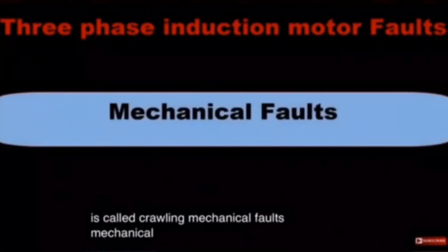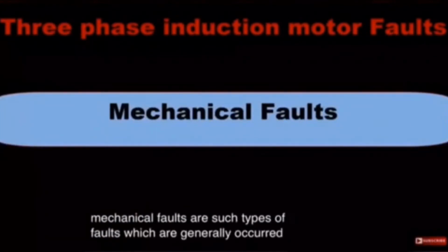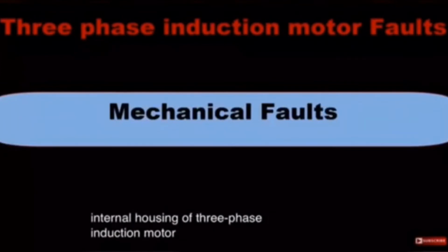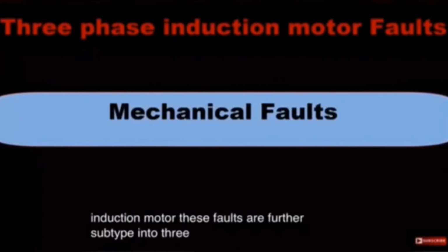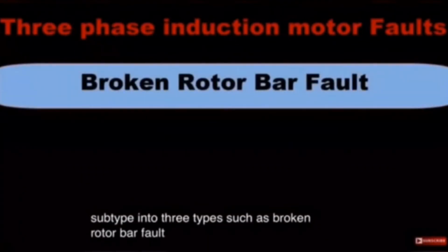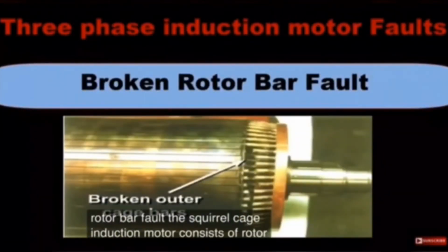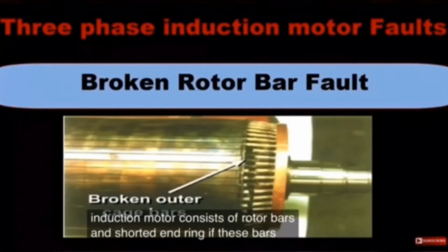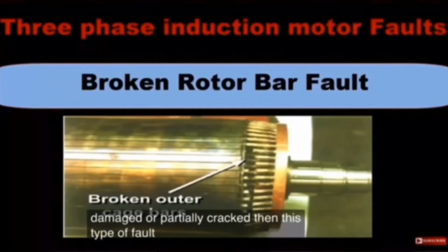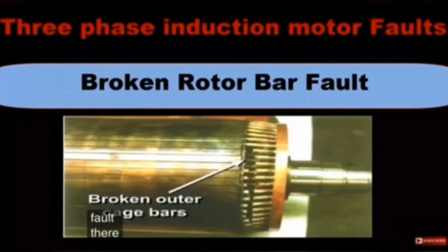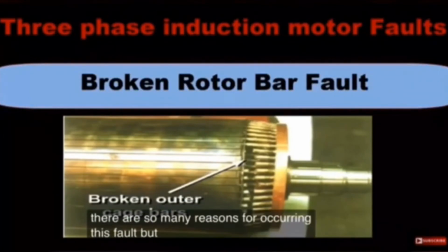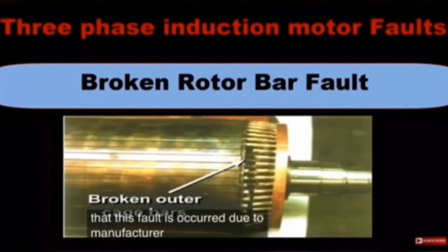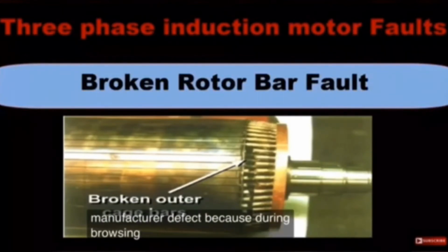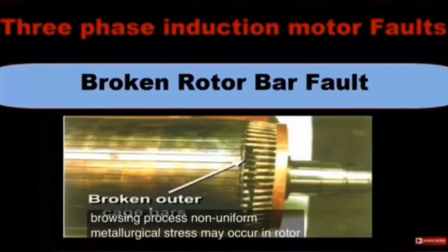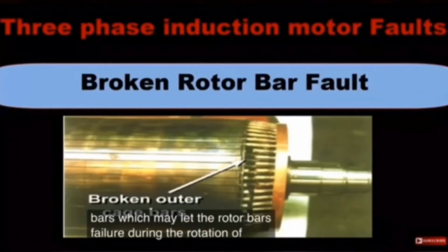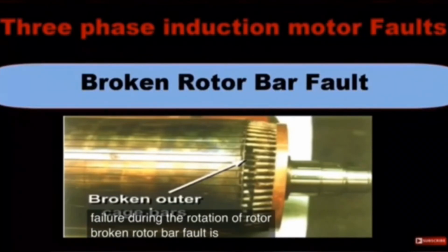Mechanical faults. Mechanical faults are such types of faults which generally occur in the internal housing of a 3-phase induction motor. These faults are further subdivided into 3 types such as broken rotor bar fault. The squirrel cage induction motor consists of rotor bars and shorted end ring. If these bars are damaged or partially cracked, then this type of fault is called rotor broken bar fault. There are so many reasons for this fault, but it has mainly been observed that this fault occurs due to manufacturer defect. Because during brazing process non-uniform metallurgical stress may occur in rotor bars which may lead to rotor bars failure during the rotation of rotor. Broken rotor bar fault is shown in figure.